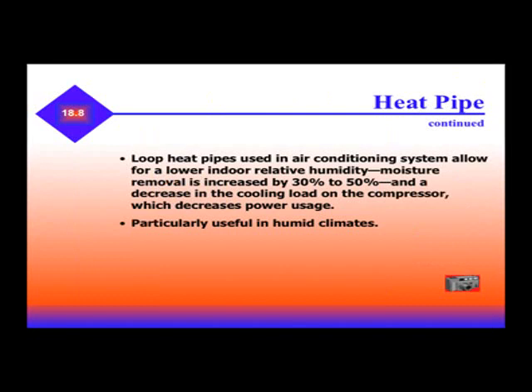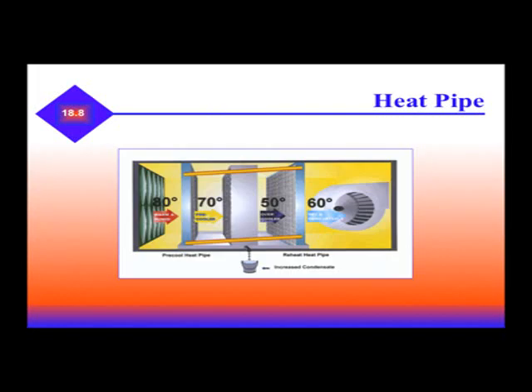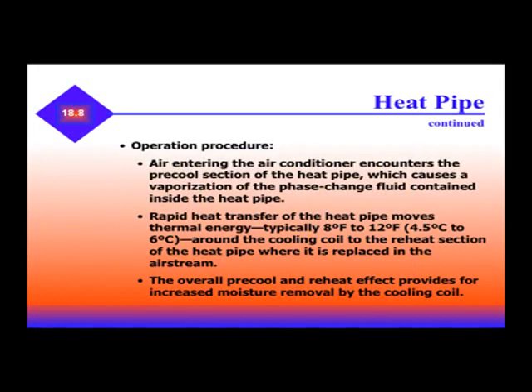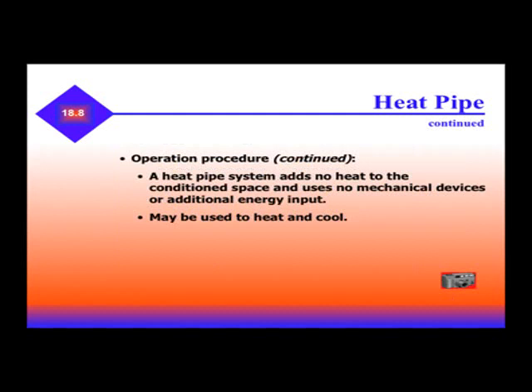Remember, in air conditioning, one of the highest uses of power is the removal of humidity, and the heat pipe is particularly useful in very humid climates. Air enters the air conditioning and encounters a pre-cooled section of the heat pipe, which causes vaporization of the phase change fluid contained inside the heat pipe. Rapid heat transfer moves thermal energy about 8 to 12 degrees around the cooling coil to the reheat section of the heat pipe, which is replaced in the airstream. The overall pre-cool and reheat effect provides for increased moisture removal by the cooling unit. A heat pipe system adds no heat to the conditioned space and uses no mechanical devices or additional energy input.